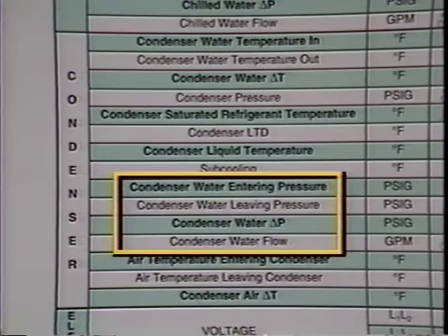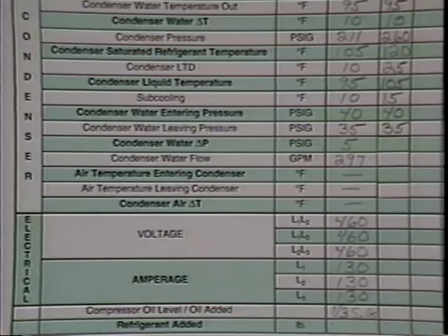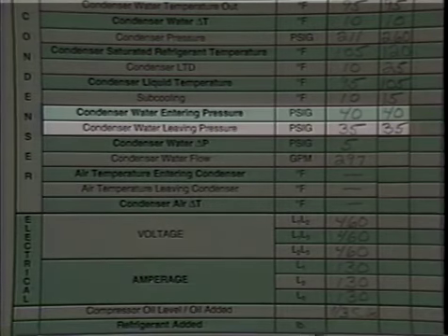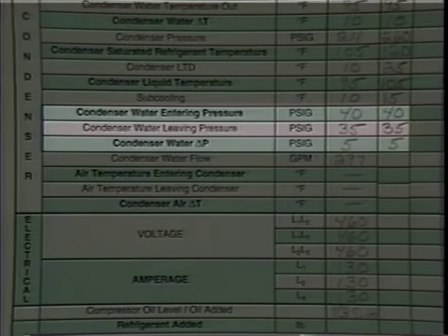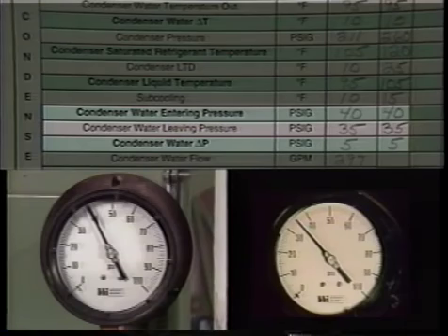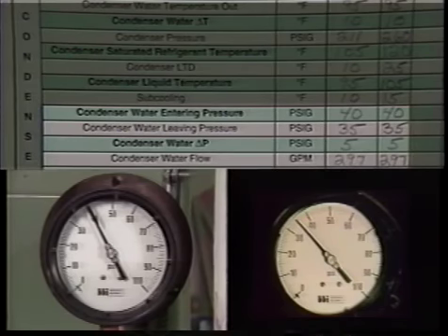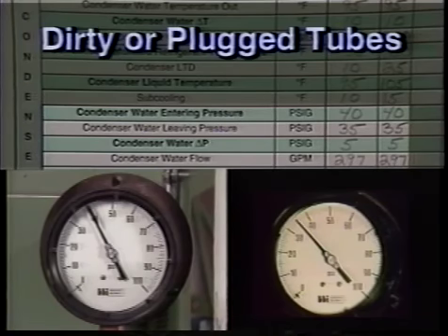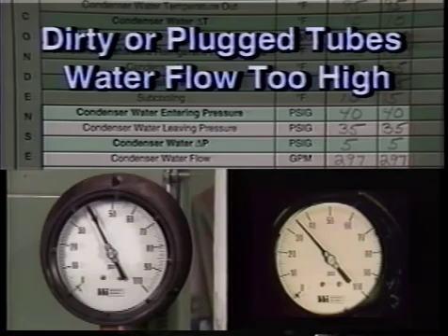Condenser water flow. Space is provided on the log sheet to record the entering and leaving water pressures. The difference between the two readings, or delta P, indicates a pressure drop of the water flow through the condenser tubes. The same gauge should be used for both readings to ensure accuracy. This pressure drop can be compared to the design pressure drop to determine GPM, and if greater than design, there is the possibility that the tubes are either dirty, plugged, or the flow is too high.